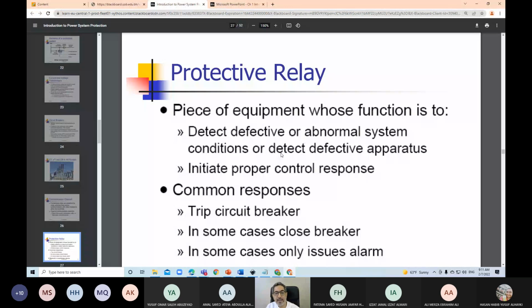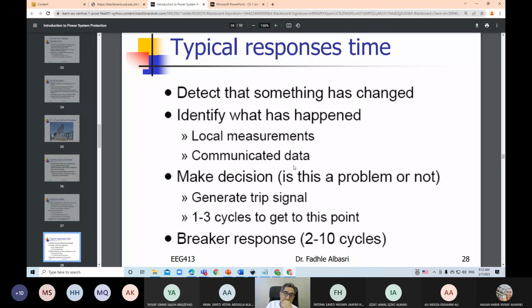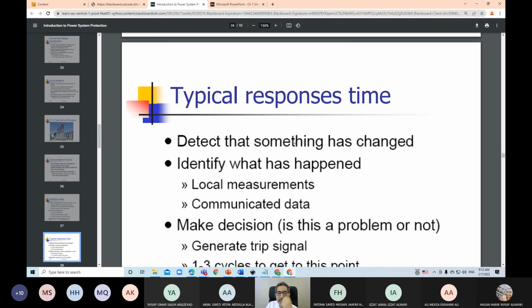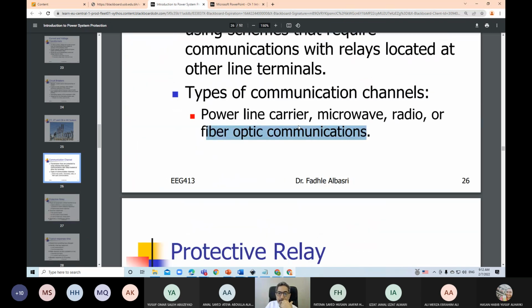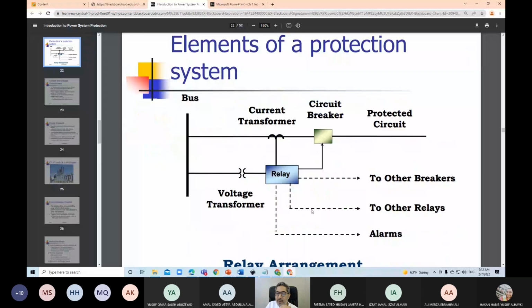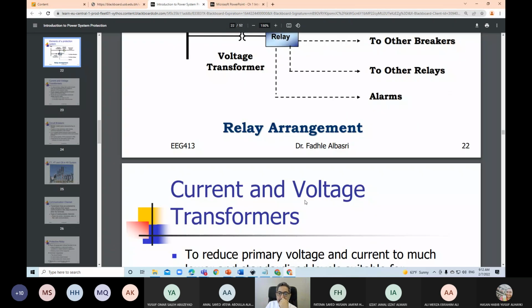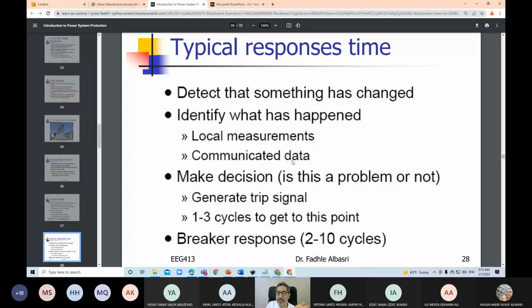How fast a relay detects a fault and clears it depends on the technology. Relays detect a fault based on either local measurements, like we are in a substation and these are local measurements, or based on information received from the other side, from other relays. They call it a remote end. So we can use local information or information received through the communication channel, so that we identify if there is an abnormal or fault condition.